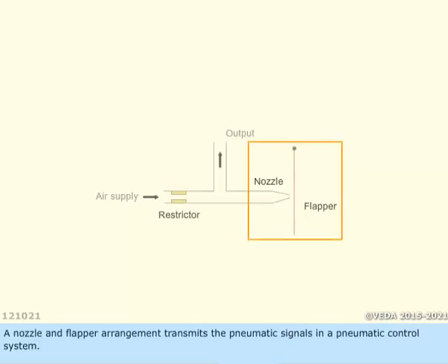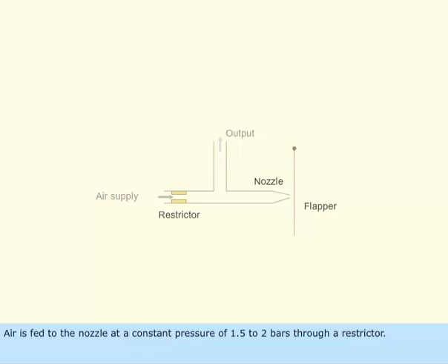A nozzle and flapper arrangement transmits the pneumatic signals in a pneumatic control system. Air is fed to the nozzle at a constant pressure of 1.5 to 2 bars through a restrictor. The function of a restrictor is to limit the air flow.